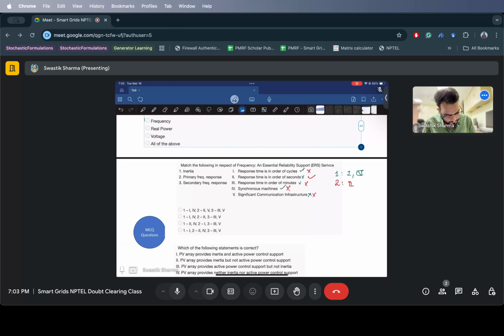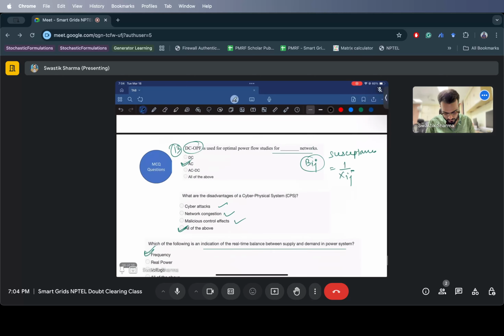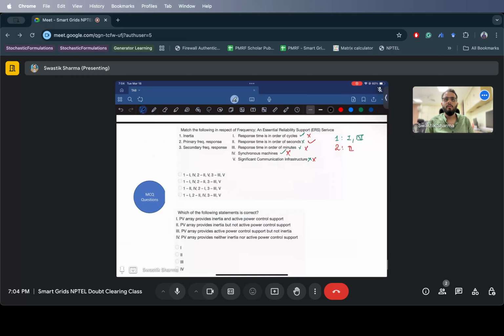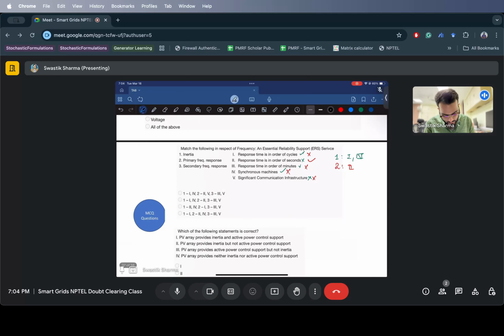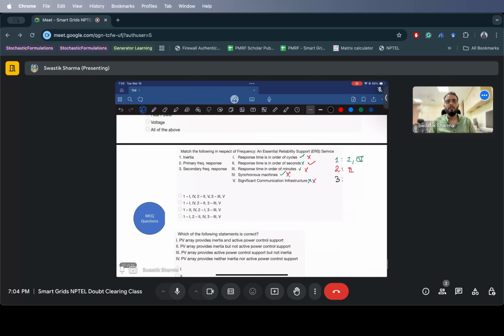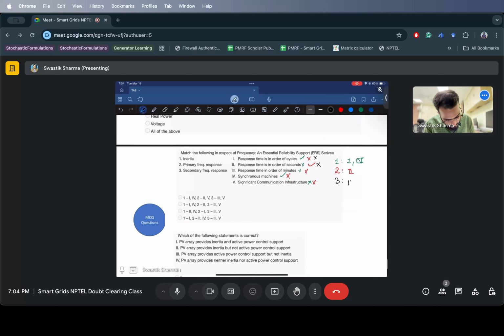Next, secondary frequency response. This is not in the order of seconds, it's in minutes; the response kicks in within a few minutes. It is not limited to synchronous machines only. It does require significant communication infrastructure, because now you have to issue AGC commands to the respective generators.